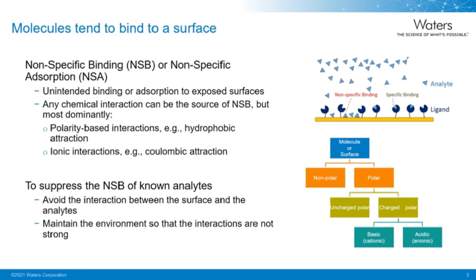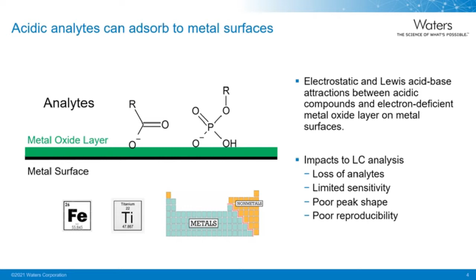Expanding upon nonspecific binding for liquid chromatography, many of us know that acidic analytes in particular disappear during analysis, and this is because of the metals that modern LC columns are made with. Either stainless steel, titanium, and any other metals can lead to this adsorptive loss. And these metal analyte interactions are driven by Coulombic attractions such as electrostatic or Lewis acid-base type attractions, which are typically much greater than the polarity-based attractions. And so the result is that we can lose our analyte peak or only retain a portion of what we inject. It can also, as you can see on the right, lead to poor peak shape and also poor reproducibility.